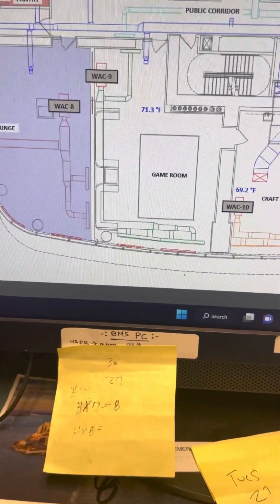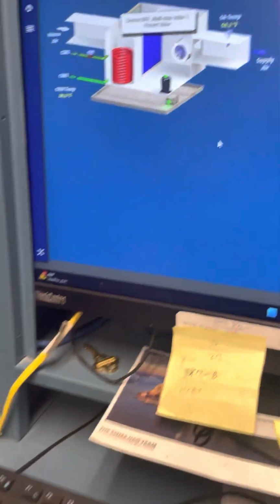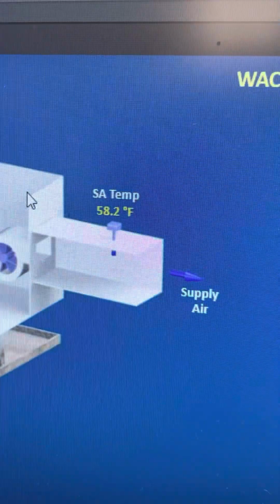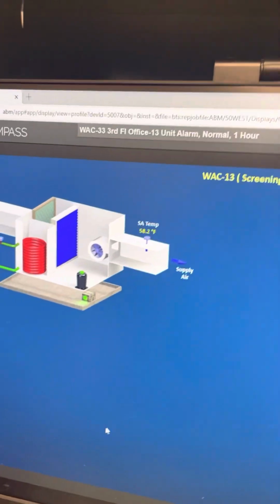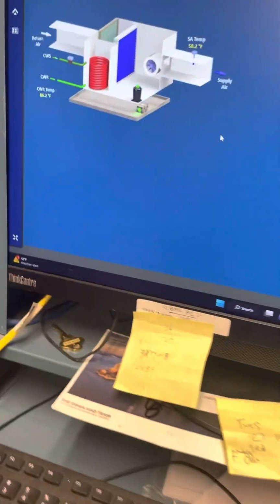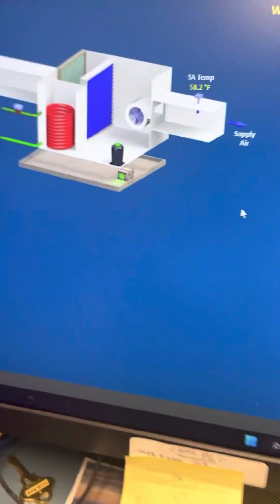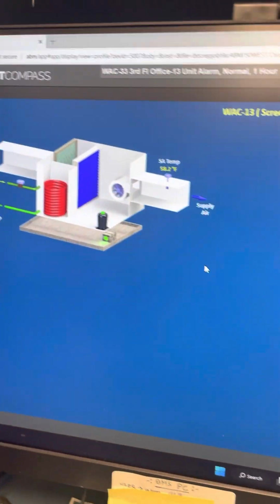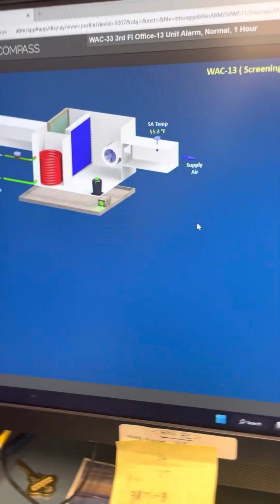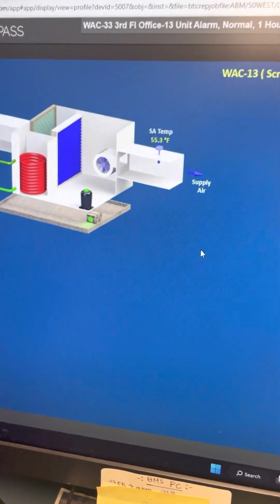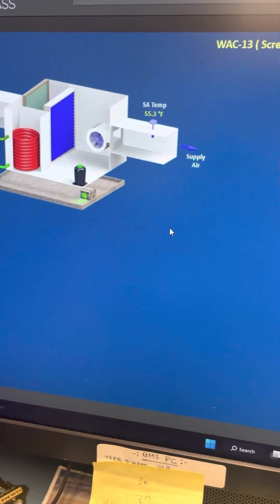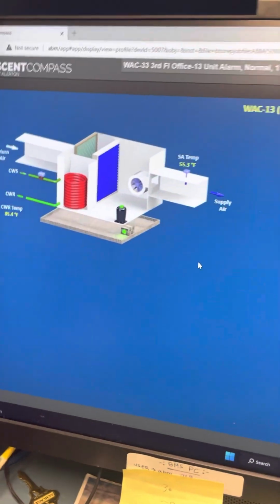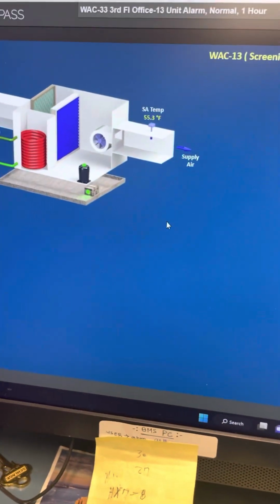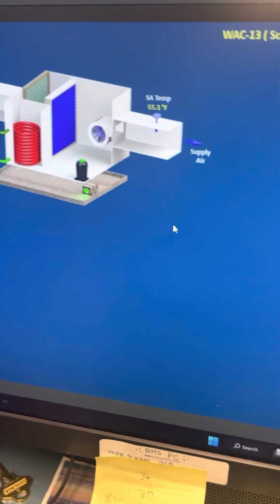Still hasn't peeled any temperature off the space temperature yet, but you see here we have 58.2 degrees Fahrenheit supply temperature, which is pretty good. I like anything 55, 57, 50 is okay. I don't like anything cooler than that because it runs the risk of freezing the coil if it gets closer to the 30s. If it's in the 30s, you have too much charge, and then you have other things you have to do to fix that.